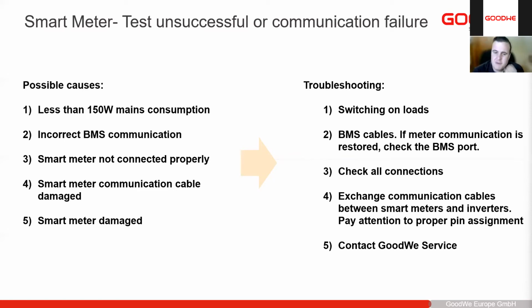If there's any problems with that supplied BMS meter cable, sometimes because they are fixed when we're running them neatly in trunking, they can get damaged, and then you might need to replace that. And lastly, which hardly ever happens, you might have a faulty smart meter, when you can contact support to get a replacement.